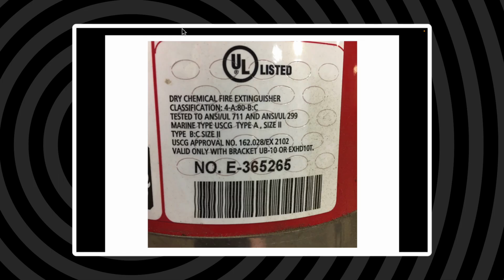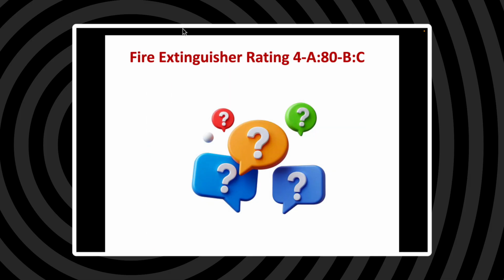To do a quick look, you can look at an extinguisher in your workplace. It'll have a label on it, like the one you see up on the screen. If you'll notice, there's a classification on this extinguisher. It says 4A80BC. Well, what in the world does that mean? It means that it has an A rating for that wood and paper that we talked about. It has an 80 rating for B fires, flammable liquid fires. So let me get into this a little bit more so you understand it. What does that 4A80BC really mean?